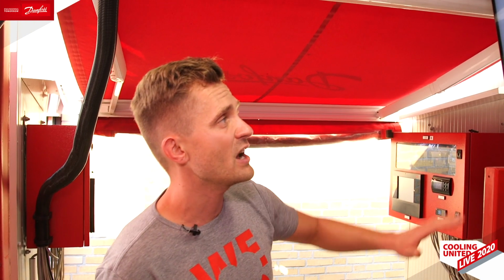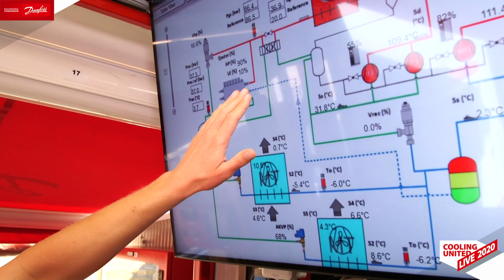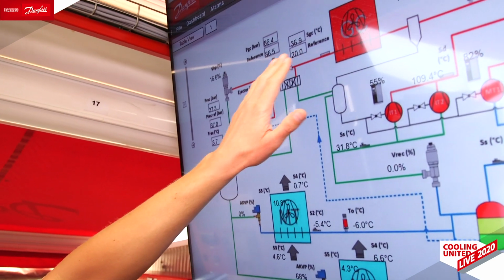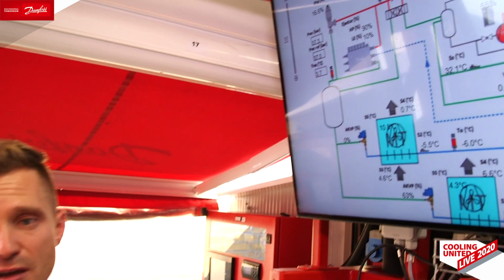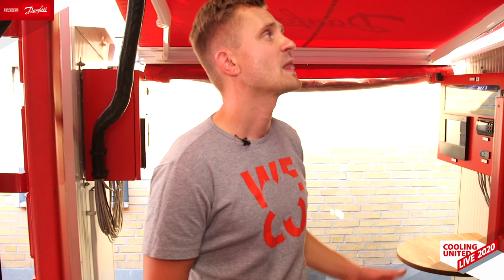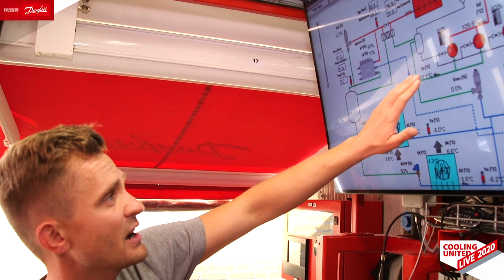It is designed in a way to lift some gas leaving the MT cases, mix it with the gas leaving the gas cooler, and send it to the receiver at the medium pressure level. In the next step, the pre-compressed gas is taken by the IT compressors, which operate more efficiently thanks to the lower pressure lift required.